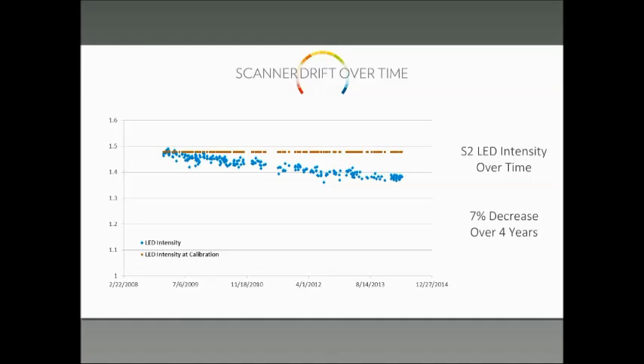There are internal calibrations built into the S2 and the S3 that account for this fading. We put in internal calibration standards in terms of detectors and light sources that allow us to accurately measure the brightness of the LEDs as they age, and also the change in the sensitivity of our detectors as they age. The internal calibration standards are able to take out drifts such as the one shown here.